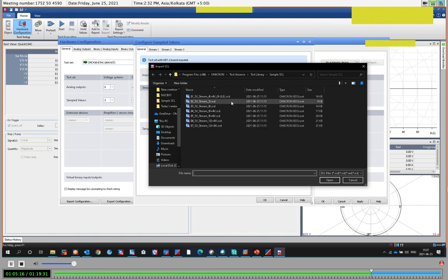If you look, it's not fully 9-2-LE. Just on the top, what we have is 9-2-LE, the UCA implementation guideline, the 9-2 Lite Edition. Now you can see all other files have configurable or flexible data sets. This is a really nice new feature, and we have implemented it fully in our device. If you want, you can even have 12 currents and 8 voltages within one sample value stream. The IED or merging unit which allows this, you can try it. It will be available to all of you soon.